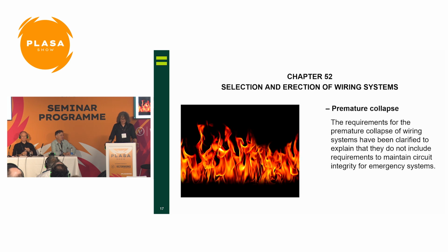So next thing to look at is premature collapse. What happened here was there were two incidents in the UK where firefighters had gone into a building, and because of the way that cables had been lashed up using nylon cable ties, with the heat of the fire, not particularly the flames, but the heat of the fire wafting down a corridor, it melted the method of holding the cables up.